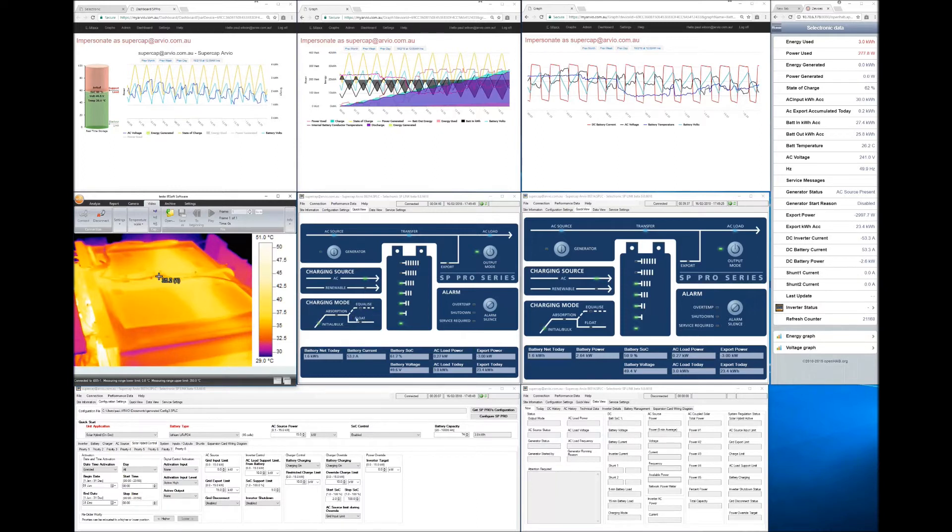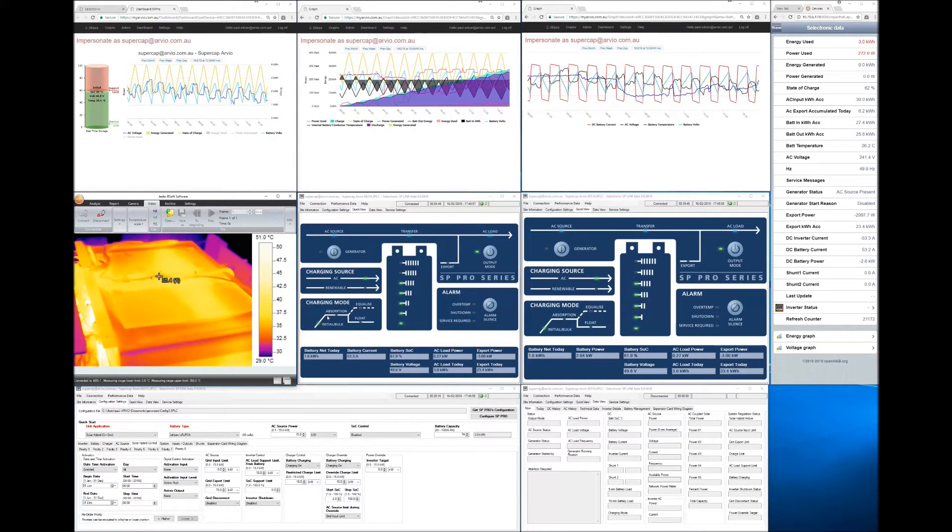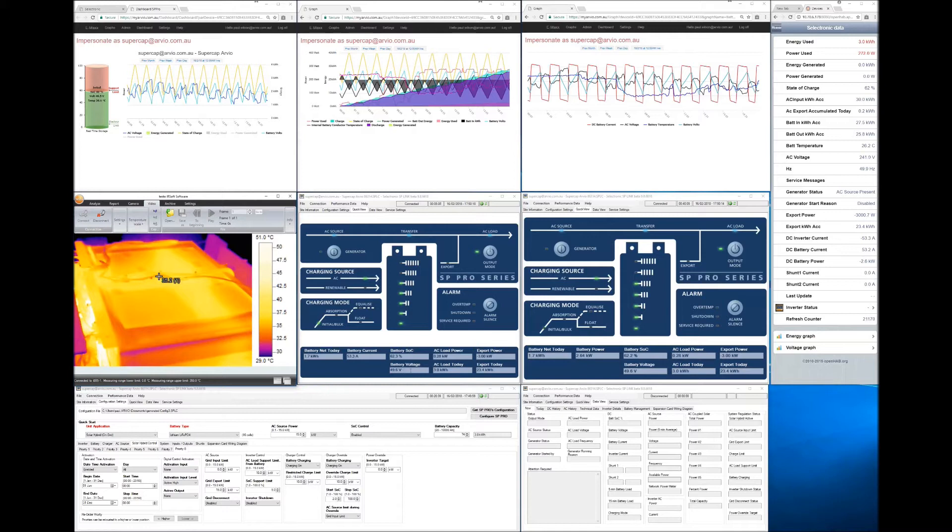Now lithium batteries are a little bit different but they all have a certain charging regime. Being a supercapacitor we don't have to actually charge in a certain way. We just give it full bulk charge all the way until it's full. At the moment we are charging here at 53.2 amps. And the battery state of charge says it's 62% but that's not quite accurate because the inverter can't report below a one hour rating. The battery voltage is 49.6 and we are charging so you should see that start to climb here as we go along.